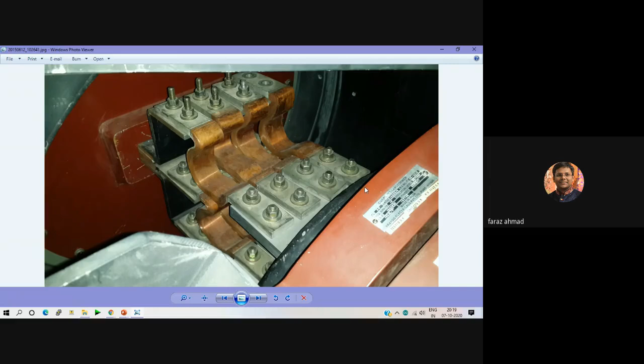You don't take auxiliary windings of the existing current transformers for the same purposes. So you install different transformers for it just because of reliability. Because reliability is the only thing that is going to save your machine. So there are many protective schemes. Differential current is calculated. If there is some differential current above certain limits, then the machine has to be halted, stopped. So many. This is used for protection and metering both.